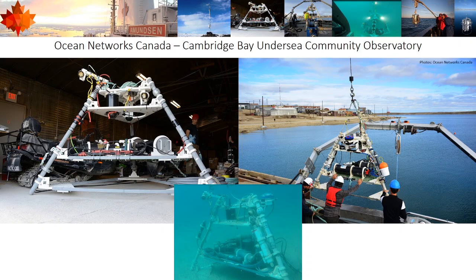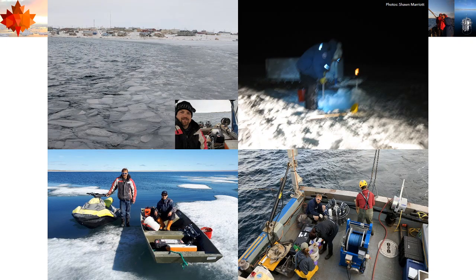And this is important because no matter where you deploy these sensors, however harsh the conditions are, you do want to be taking validation samples throughout the deployment to detect for drift or offset, and then be able to correct for drift or offset. And some conditions are more extreme than others. You can see in the fall, and then in the winter, in January, it's pretty tough.